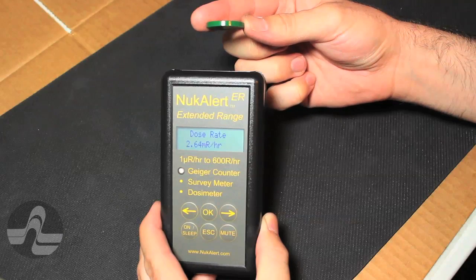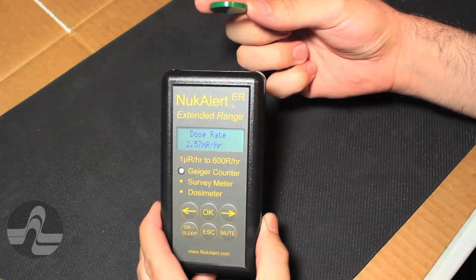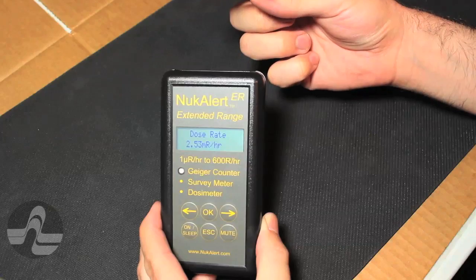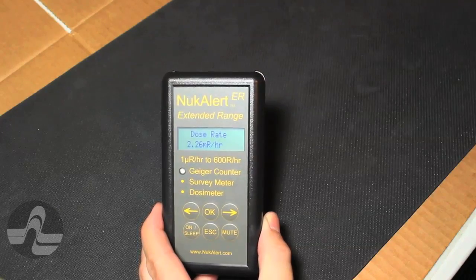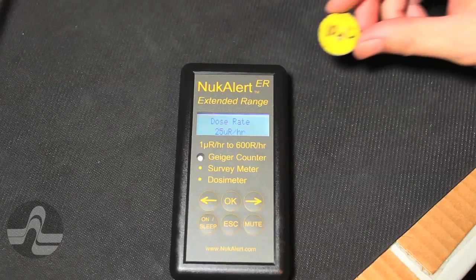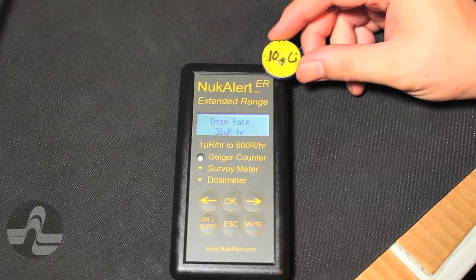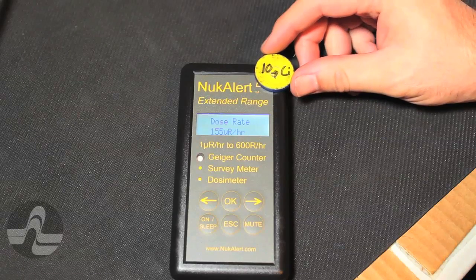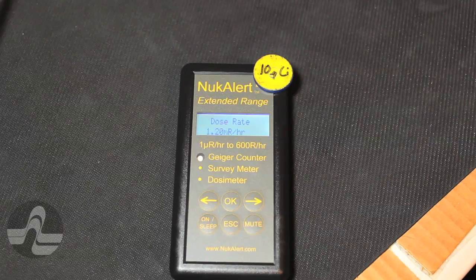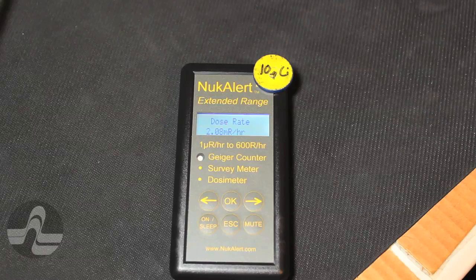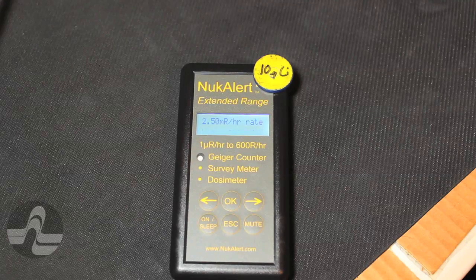Every Nucalert ER is calibrated using an NIST traceable Cesium-137 source at 600 R per hour. A dose rate alarm can be set at a variety of levels. Here, the threshold is set for 2.5 mR per hour. Once tripped, the alarm continues to sound until it is acknowledged.